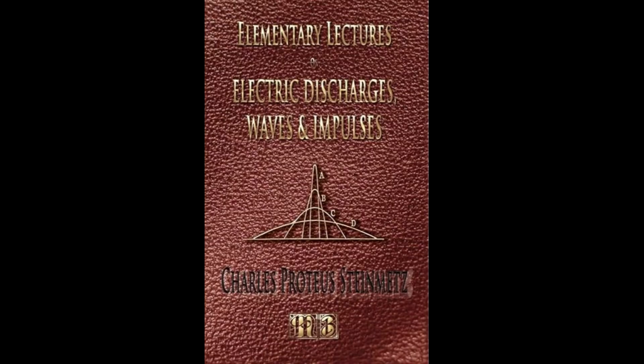This excess field current shows curious pulsations, of single and of double frequency, and in the beginning the armature currents also show asymmetrical shapes. Some oscillograms of three-phase, quarter-phase, and single-phase short circuits of turbo alternators are shown in Figures 25 to 28. By considering the transients of energy storage, these rather complex-appearing phenomena can be easily understood, and predetermined from the constants of the machine with reasonable exactness. In an alternator, the voltage under load is affected by armature reaction and armature self-induction. Under permanent condition, both usually act in the same way, reducing the voltage at non-inductive and still much more at inductive load, and increasing it at anti-inductive load, and both are usually combined in one quantity, the synchronous reactance X0.